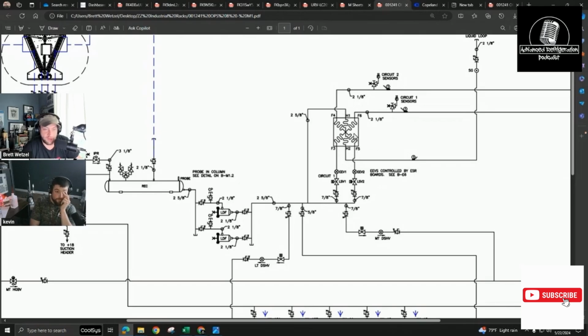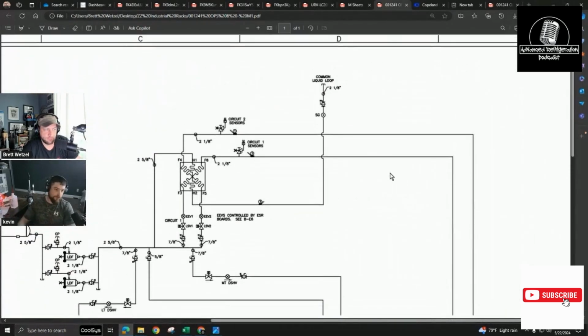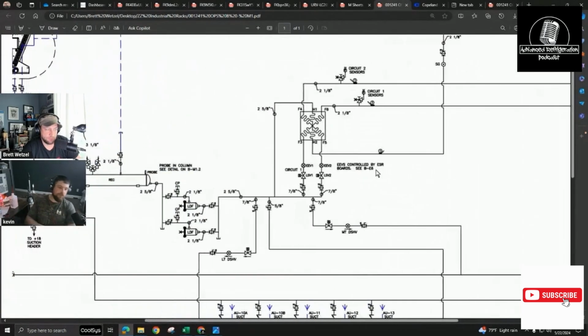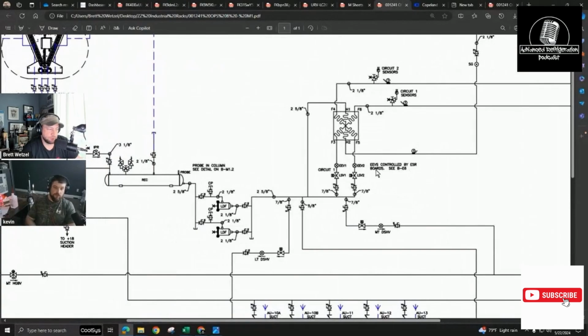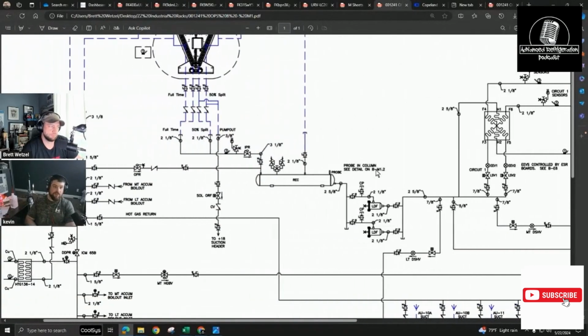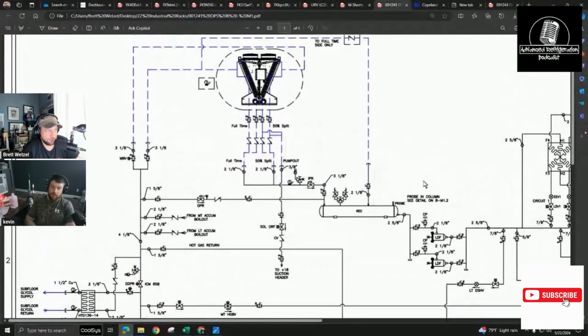I think it would be more efficient either way if you cross feed it. From what I've always been taught, cross feeding is more efficient - you use more surface area of the heat exchanger. Generally you're going to see stuff cross fed, I've never seen it where it's not, not saying it's not out there, but generally the Costco zero zone racks are cross fed.